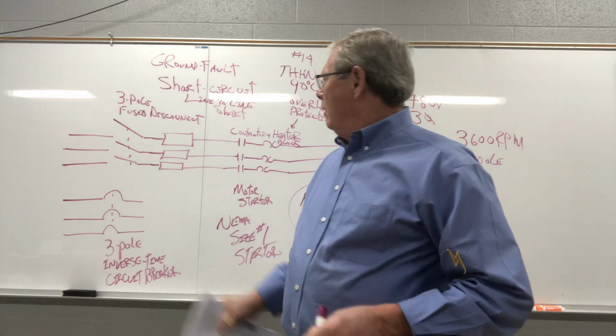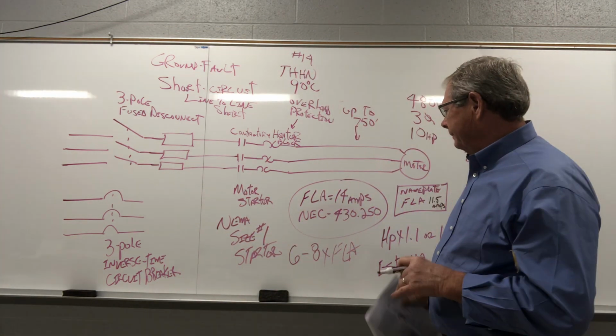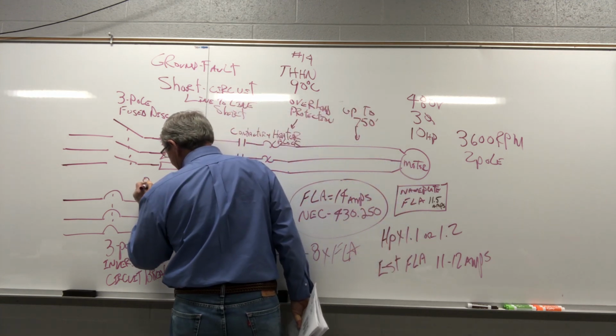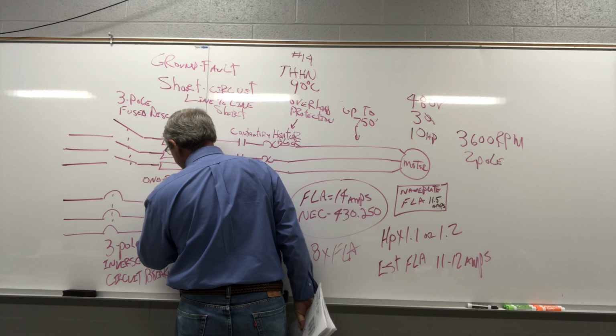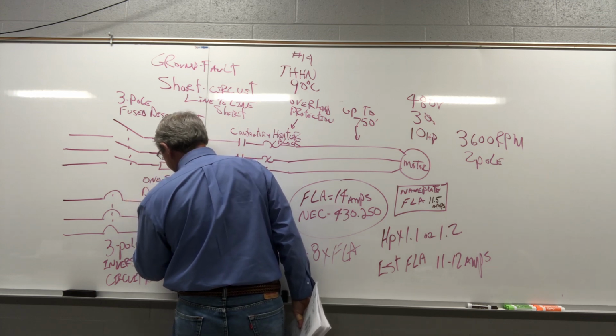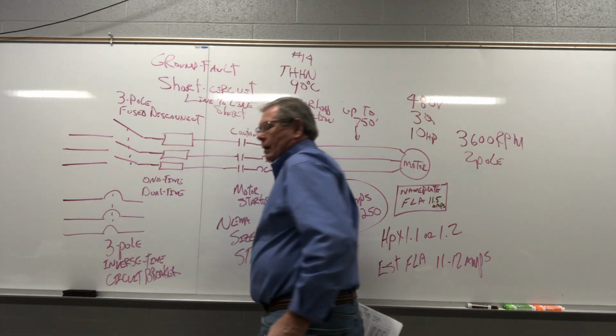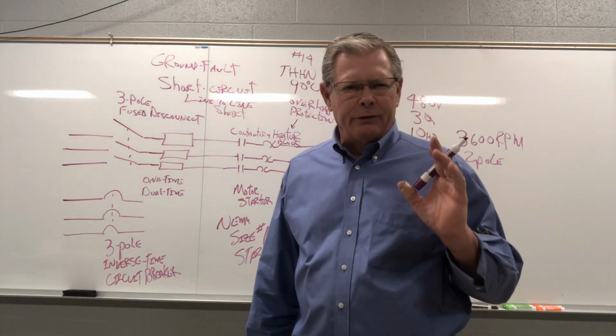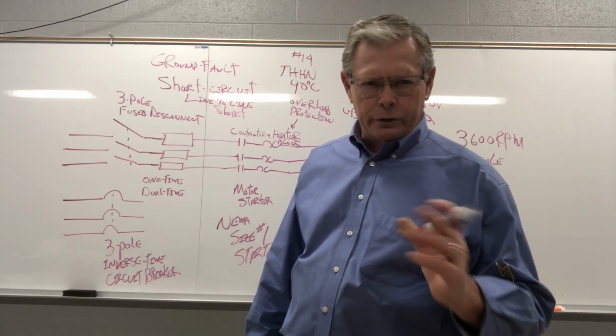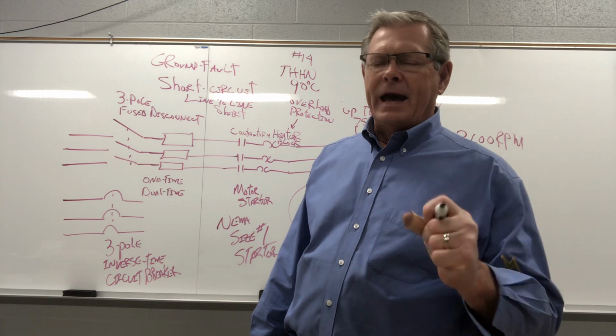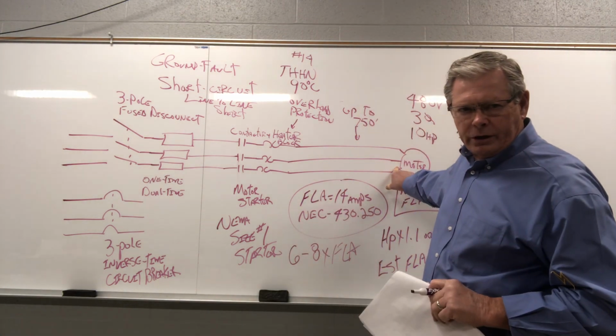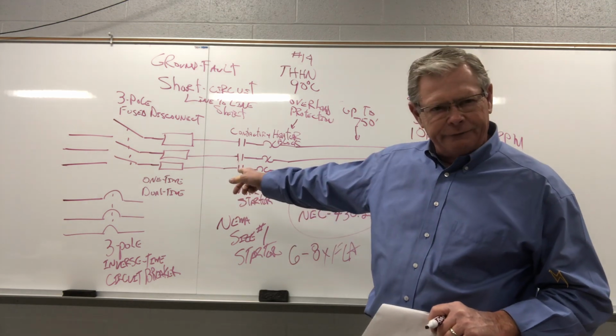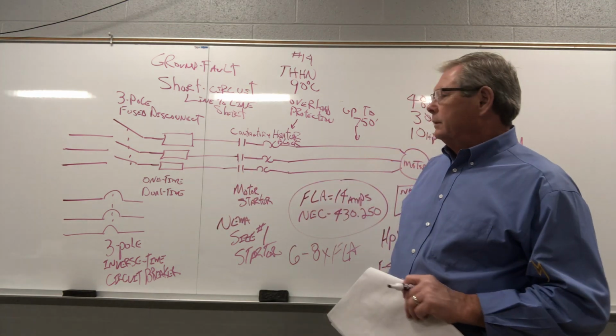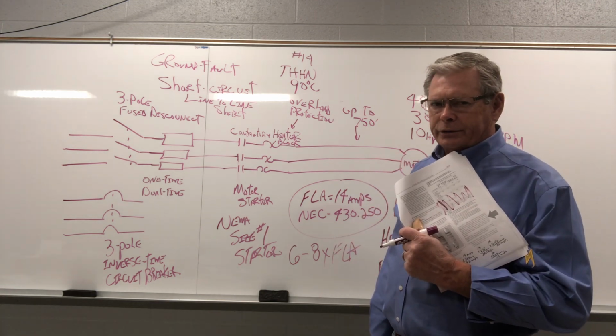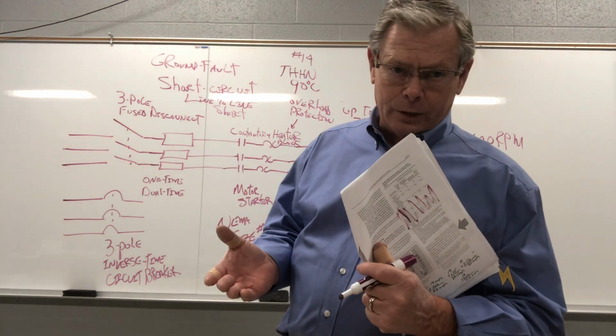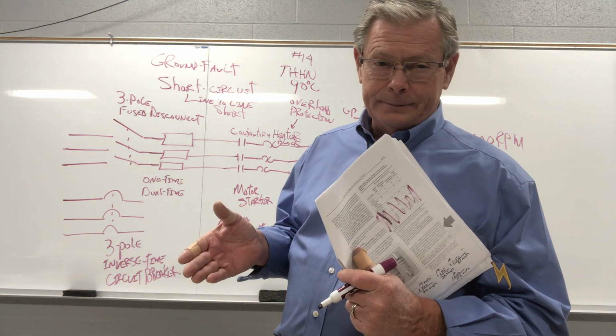Now, we're going to take this one step at a time, okay? Now, we have one-time fuses. We have dual time. And the fuse that's made for motors is a dual time or a time delay or a dual element fuse. They're all the same. Remember, when your motor starts, you got that motor current running through it, it's gonna be heating the wires. It's gonna be heating the fuses or the circuit breaker too, you know? So, they make dual element fuses for motors. One-time fuses are not made for motors, but we could use them if we had to. And I'm gonna show you how here in a minute.